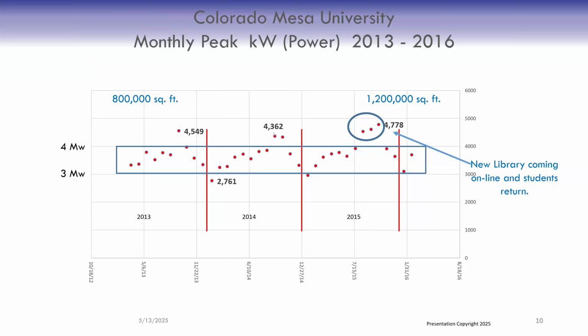I'm sorry I didn't have a chance to update this with the new information we got. For example, when we had about 800,000 square feet attached to the campus, you can see those dots, which is electric demand somewhere between 3 and 4 megawatts. As we expanded the campus up to 1,200,000 square feet, we added 50% more, but it still stays in that same range because of the geothermal, the load shedding, and the diversity we have.